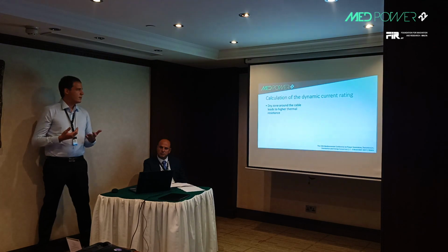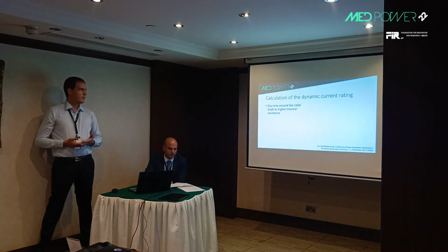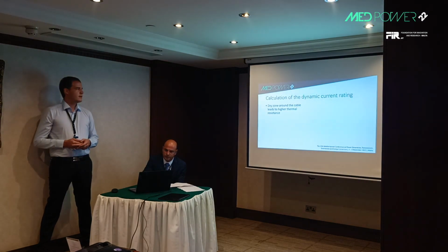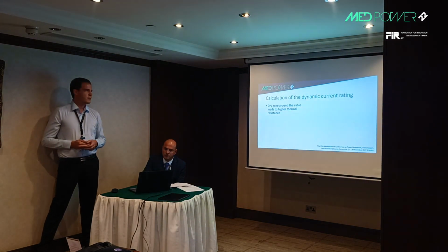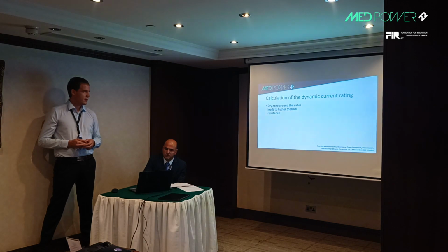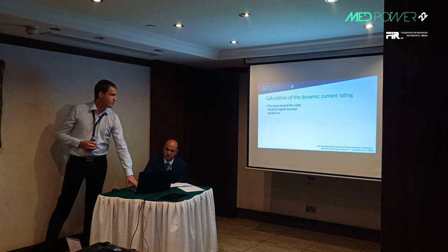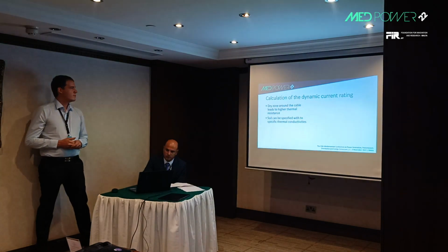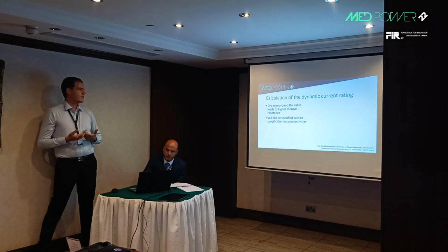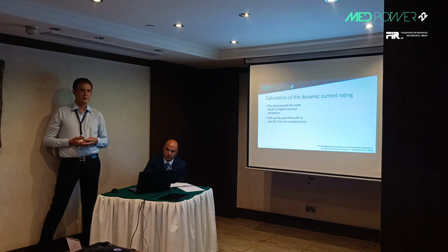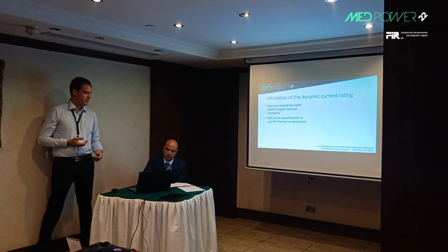and if the cable is too warm, then we get a dry zone around the cable, and this leads to a higher thermal resistance around the cable, and then the ground dries out, and so we can specify two different thermal conductivities, one for the dry zone and one for the wet zone.